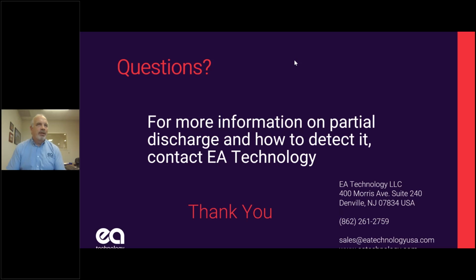However, over time, electrical trees or water trees can dry out, and now I have a void where that water was, and that void is going to become an electrical tree, and that will generate a fair amount of PD, which can be seen either in a PD test or when you do a forensic investigation. I showed you those microscopic pictures of the electrical trees. They will lead to failure because the PD will advance until the insulation is eaten away and it flashes over.